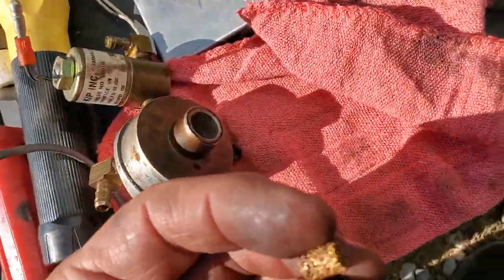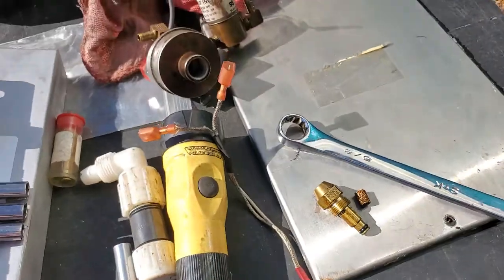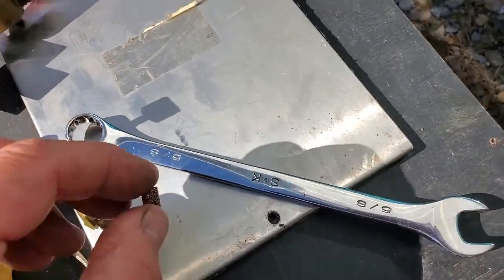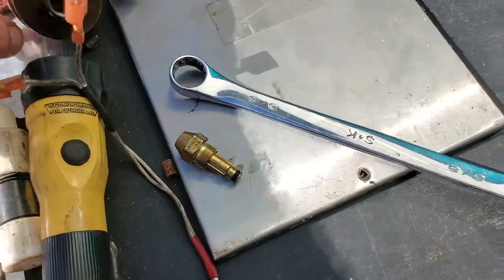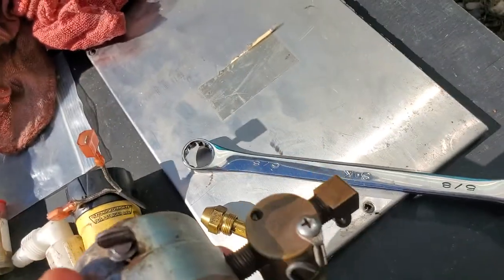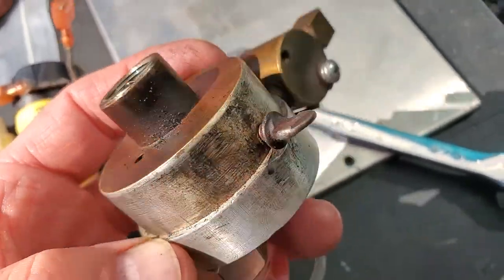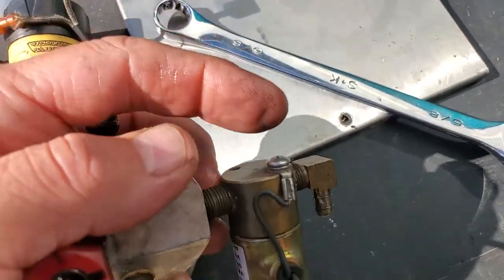So I'll put a new one in there. We're back to the nozzle — we broke it down, it was really filthy. I'm going to tear it apart and change this stone out. The fuel solenoid's got a screen in it too. Sometimes when the flame sensor gets soot on it, it can't see the flame, so the flame will start and it'll shut off. This is self-grounding right here — this is a hot signal, B-plus, battery positive, 12 volt goes to that.